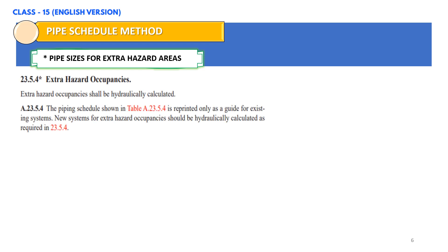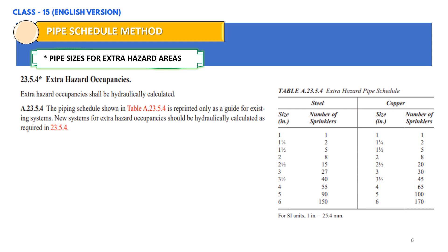For extra hazard occupancies, the pipe schedule method cannot be used. However, there are some exceptions as shown on your screen. The piping schedule shown in table 23.5.4 is reprinted only as a guide for existing systems. New systems for extra hazard occupancies should be hydraulically calculated as per NFPA 13 and cannot use the pipe schedule method.